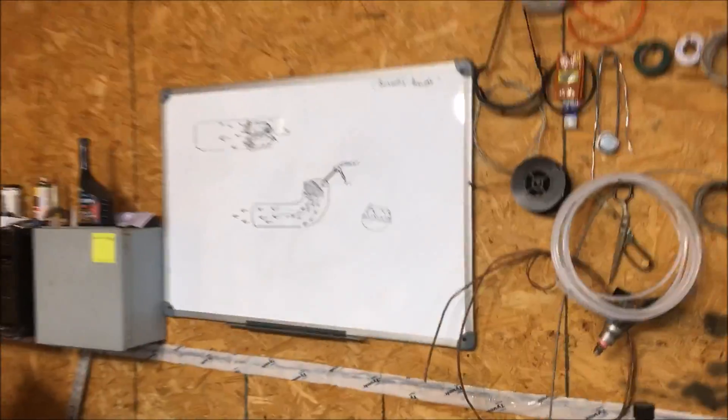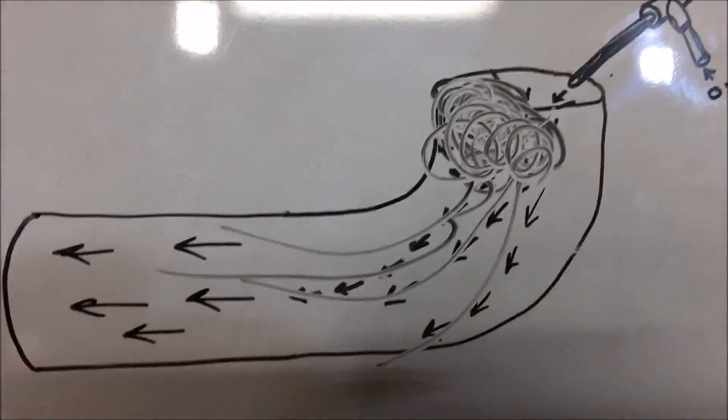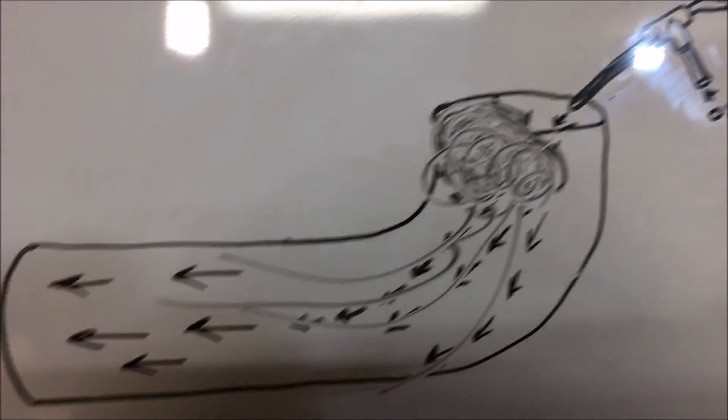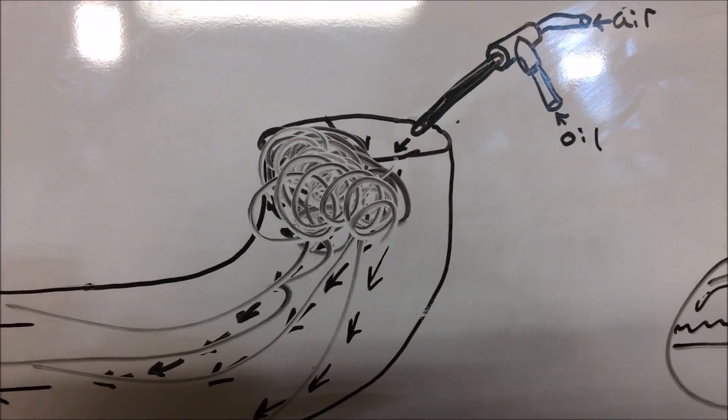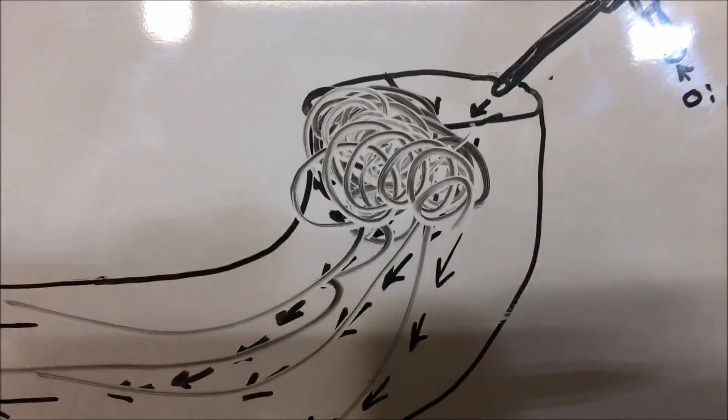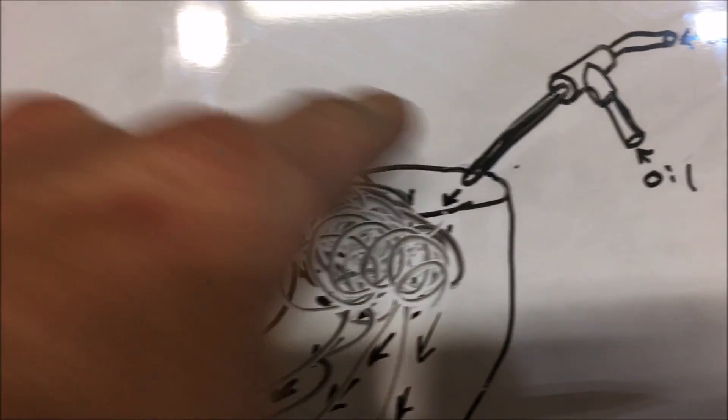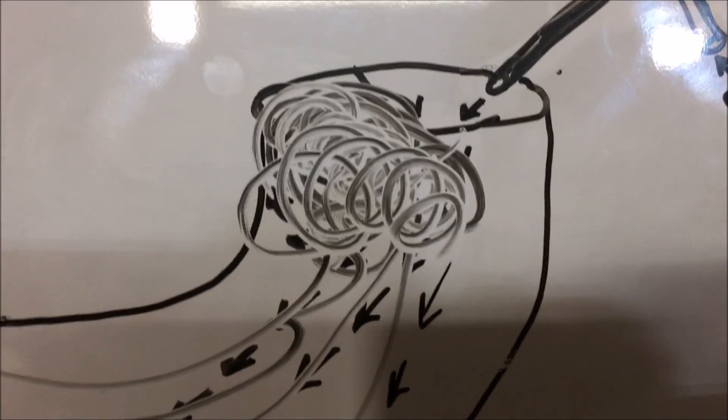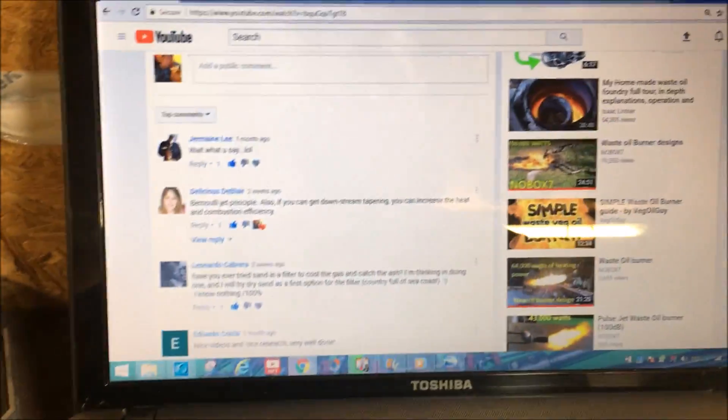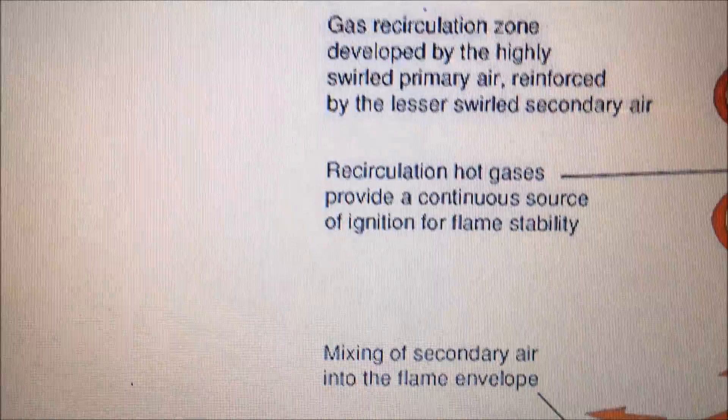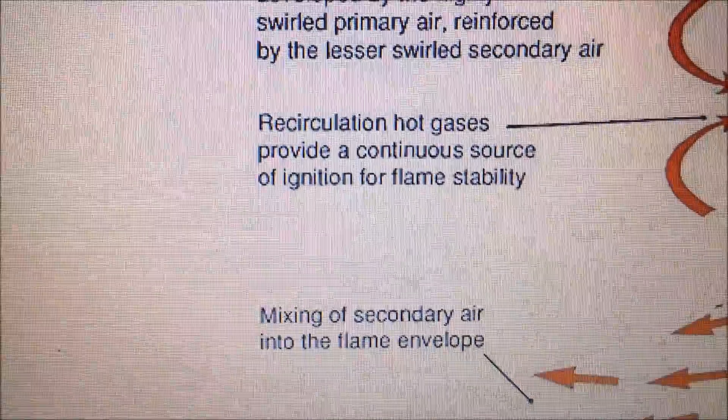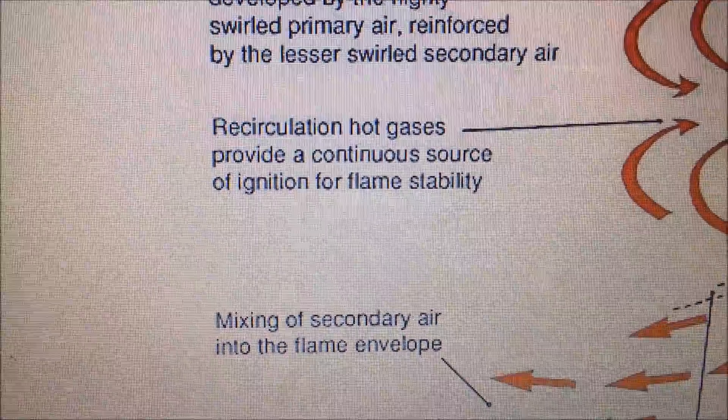I also often use the decibel meter on my phone in those locations. 100 decibels is hearing damage, 110 is severe hearing damage in a very short amount of time. This plate stabilizes the flame and makes it quieter. But there you have it - I just thought I'd share that with you on why this thing works. Hopefully the gentlemen that discussed this with me stumble on this video because it's kind of interesting. I figured it out by analyzing video footage during editing. I suddenly realized there is a rolling wall of fire in that elbow which is reigniting the gases. It came to me because of a previous observation of this quote: recirculating hot gases provide a continuous source of ignition for flame stability.